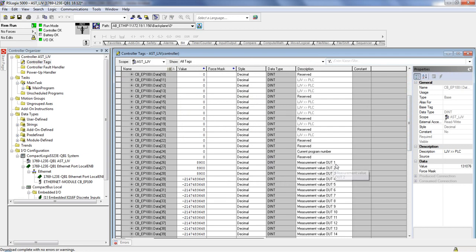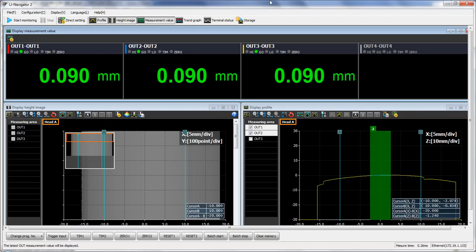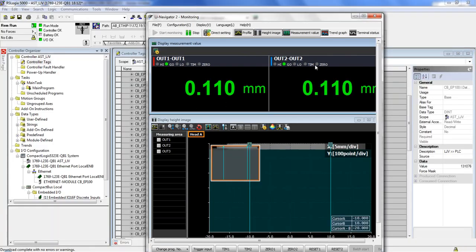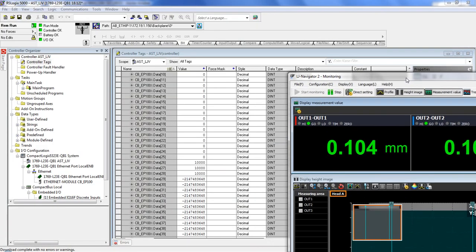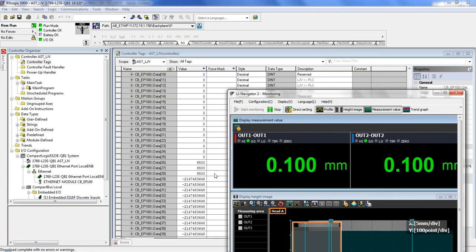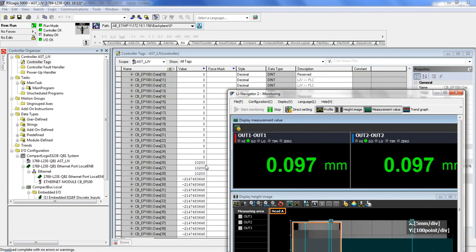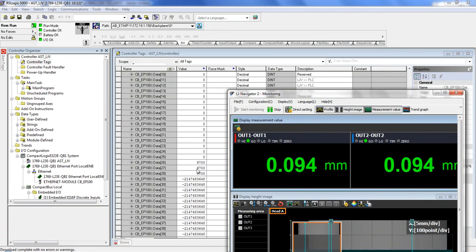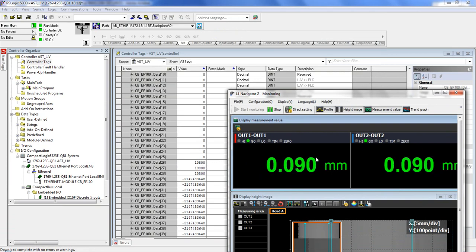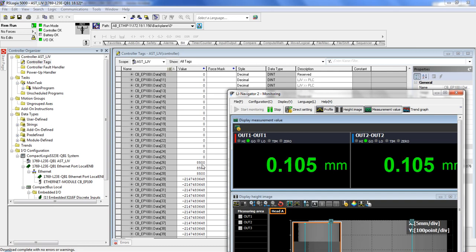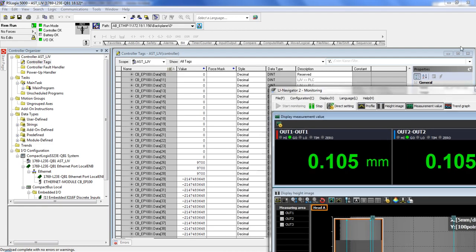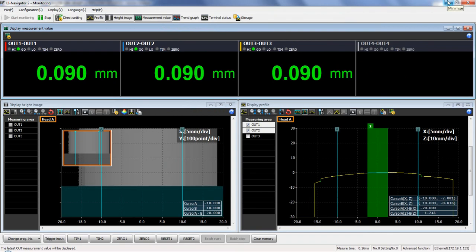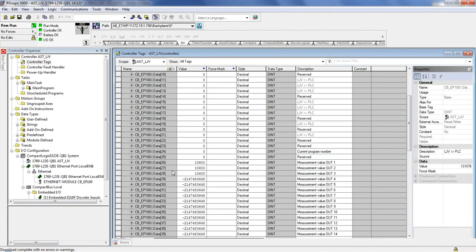Here, when I go down to my measurement values, I see my actual measurement values, some of them updating right here. So let's go ahead and pull up LJ Navigator and have a look at what we're actually seeing there. So here we see that these values reflect the numbers that I'm seeing over here. What you should remember is that these numbers that you see over here do not have a decimal point. So to get the number in millimeters, as we would see on our display, all you need to do is divide this number by, I believe it was 100,000, and you'll get the correct numbers.